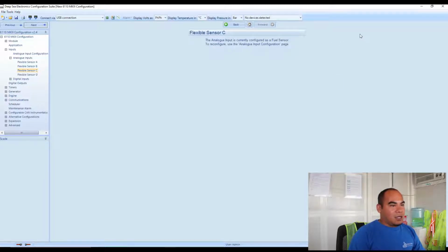You can select it in the module, in the list of your module. As I said, you can install voltage type, resistive type, and pressure type. If the sensor you are going to install is not in the list of the module, just edit the graph, and always refer to the manual of that kind of sensor in order to work properly.